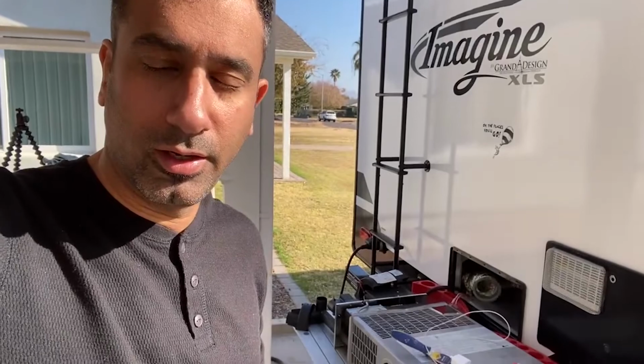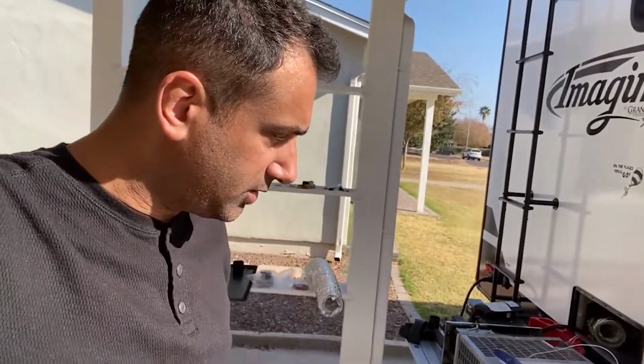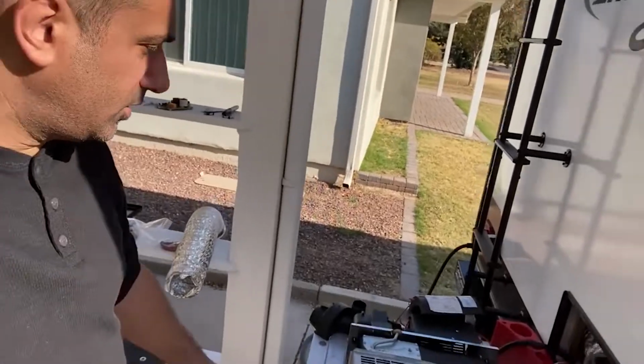Now, if you're asking yourself why I didn't start with the thermostat, it's because all the symptoms showed that one of these parts was not working, and the thermostat, essentially a simple switch of turn on, turn off, is working properly with the AC, and also, as far as we know, works with the furnace. So this is where we're at. What I'm going to do right now is install the two new parts, the gas valve and the igniter.